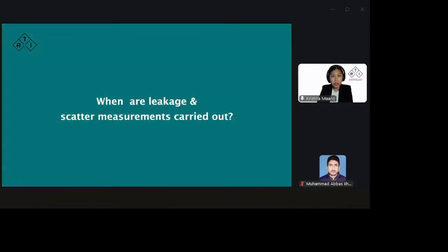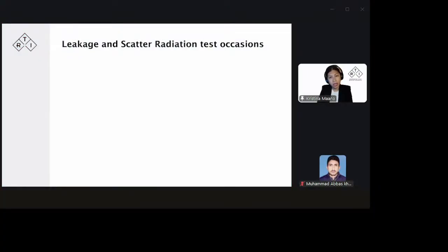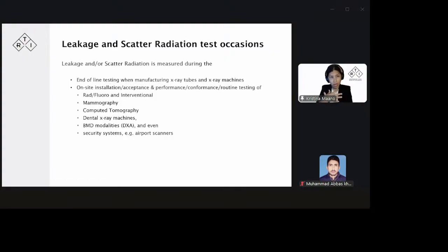Now, when do we measure leakage and scatter radiation? Let's take a closer look into this. The leakage and scatter radiation tests are usually done, I mean, for us, I am a medical physicist like you, for those who are joining us in this AFOMP webinar, in the hospitals, X-ray installations. But usually this is also done during end-of-line testing when manufacturing X-ray tubes and X-ray machines. So in the factories, there are such things as tube leakage radiation testing as well. And of course, on-site installations during acceptance, performance, and conformance routine testing of these X-ray machines.